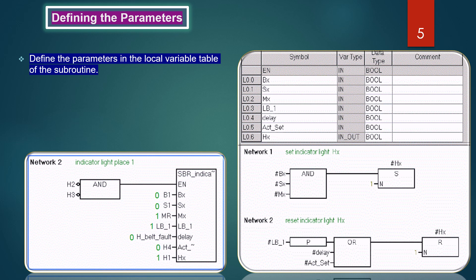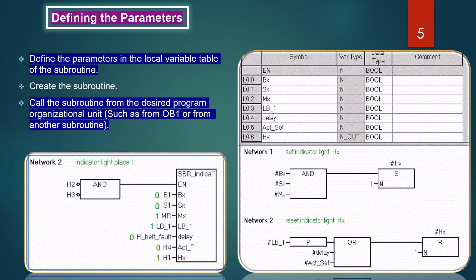To use subroutines in your program you must carry out three steps in the following order: first, define the parameters in the local variable table of the subroutine; second, create the subroutine; and third, call the subroutine from the desired program organizational unit, such as from OB1 or from another subroutine.